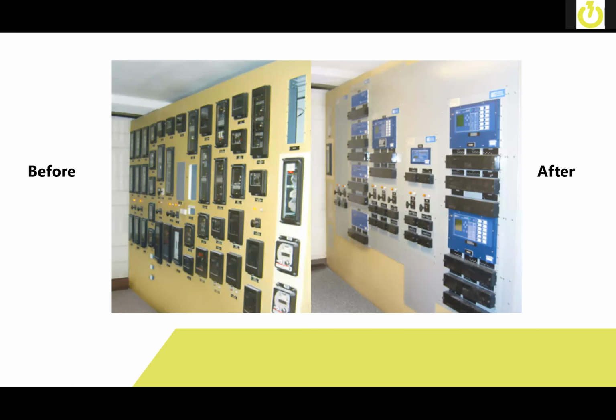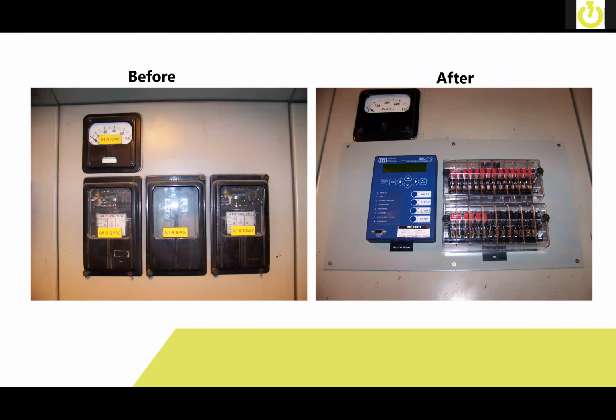This is just another example, kind of a similar retrofit, where we had a customer, again, they had some electromechanical relays that they wanted to get rid of. We went in with some full height panels. In this instance, they elected not to color match the scheme, and they wanted to go with ANSI 61 gray panels, which is what we did. Just another example, this one's of a simple feeder retrofit where the customer wanted to keep the amp meter, and we actually replaced that with a newer amp meter that they had in storage that still worked.